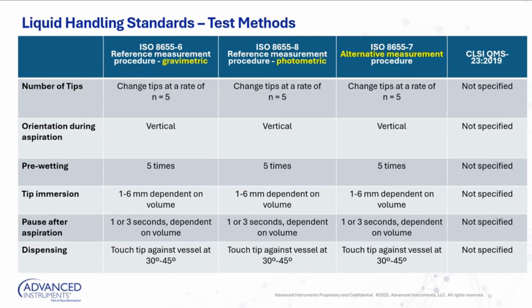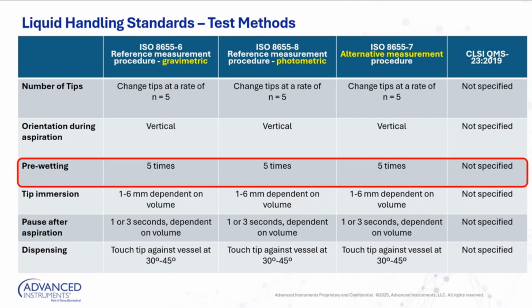Now, you might be surprised, 6 millimeters is not very deep. Oftentimes you'll see folks placing their pipette tip so deep into the solution. It's not great, right? It definitely causes some differences in results. Pausing after aspiration is 1 or 3 seconds, depending on the volume that you're working with. And then for dispensing, the ISO standards recommend that you dispense at an angle. This particular webinar is not about pipetting technique, but it is about standards. But specifically what I want to call out is this pre-wetting technique.